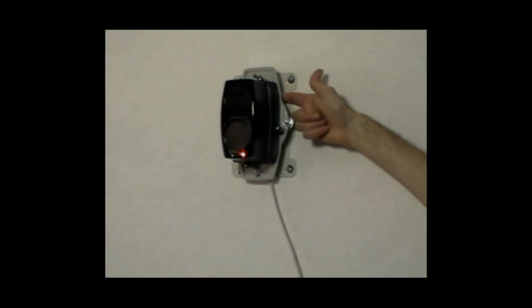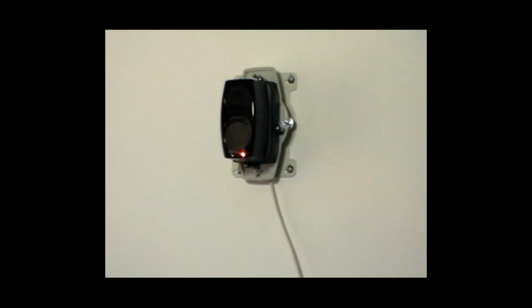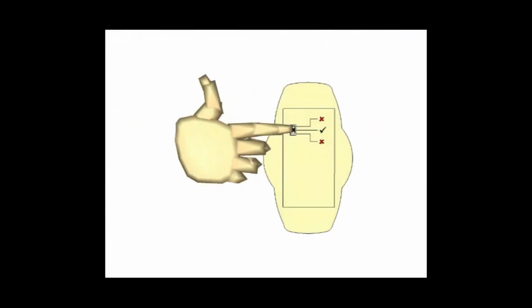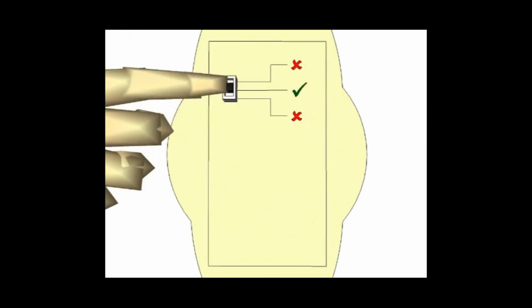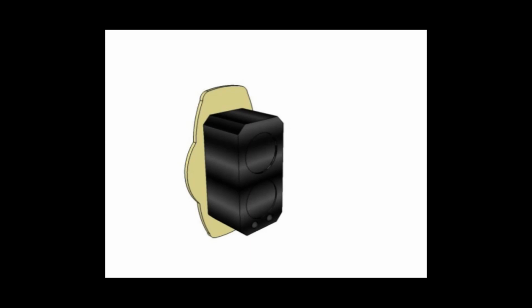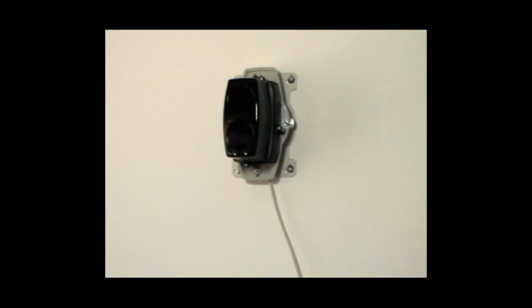Now, move the mode switch to the middle position, which is alignment mode. In alignment mode, you are centering the beam detector on the reflector and the beam detector is adjusting its power for optimum signal. The LEDs now mean something different. A red LED means that you are gaining signal, and an amber LED means that you are losing signal. Choose a thumb wheel. It doesn't matter which one you choose first. We are going to adjust both of them.